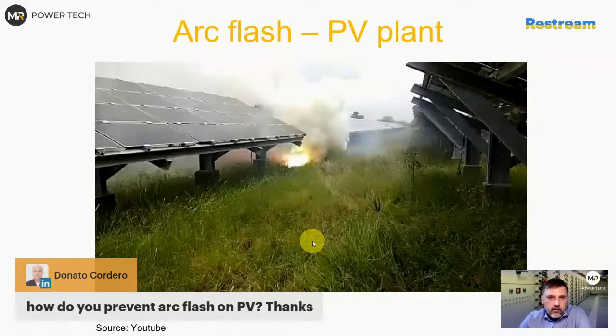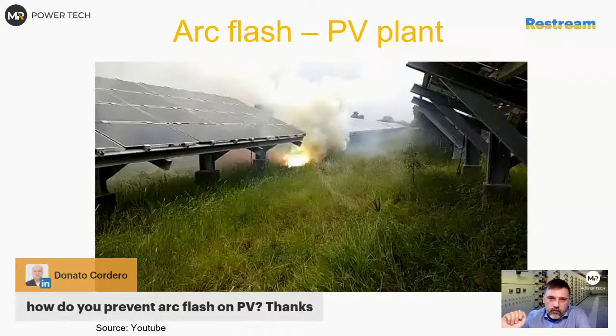It's not a direct answer to your question, but there's no direct solution for it. I've seen recently there was a post about MC4 connectors having some kind of, I'm not sure what the material is, arc box, which tries to contain the arc inside, and once it burns out, maybe it will disconnect. So at least you prevent the fire from spreading. I've also seen someone do something similar, I think plastic, with some microcapsule fire suppression tape inside. But I haven't seen the test, and I'm pretty sure it will not work for the arc flash, maybe for fire, but not for a serious arc.